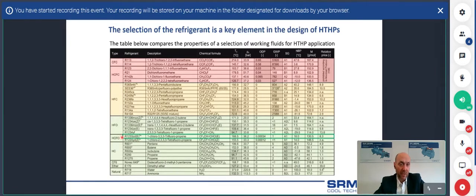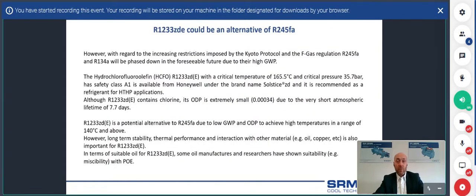In this table, we have selected the 1233 ZDE because, according to us, it has some suitable features for common heat pumps. Most of us are used to evaluating heat pumps or working with them, and know that R245fa is one of the most used, or has been one of the most used, refrigerants in these systems. Because of the Kyoto Protocol and because of its GWP value, global warming potential, it cannot be used in the near future. So one suitable refrigerant can be the 1233 ZDE, because it has a critical temperature of 165 degrees C and a critical pressure of 35 bars.